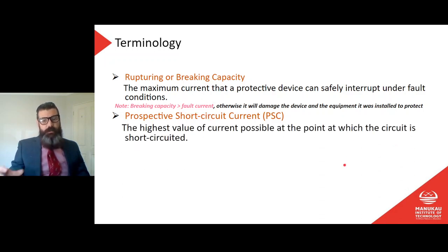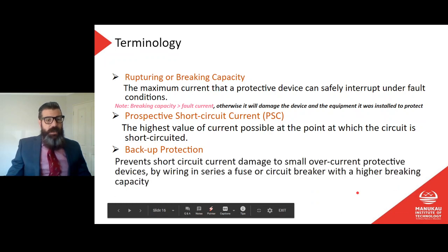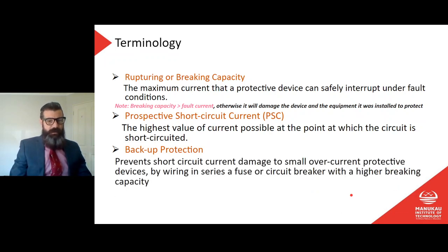Okay, and prospective short circuit current, I've just talked about that. We're talking about breaking capacity. That's the highest current possible at the point where the circuit is short circuited. So that's why we measure our earth loop impedance. What is the highest current that I could get in a short circuit situation? Backup protection prevents short circuit current damage to small overcurrent protective devices by wiring in series a fuse or circuit breaker with a higher breaking capacity.